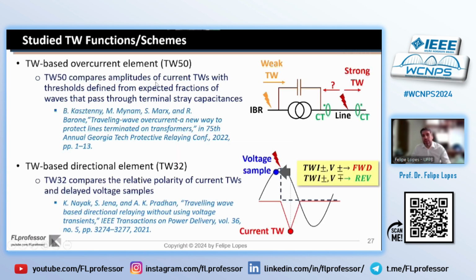The overcurrent traveling wave element compares amplitudes of currents with thresholds, which are defined from expected fractions of waves that pass through terminal stray capacitances. Such an element was presented in this paper. And the idea is if there is a line fault, it is expected to measure a strong wavefront here. But if there is a fault behind the transformer, only weak wavefronts will be measured, because they will pass through the stray capacitance of the transformer, and it will attenuate these wavefronts in such a way that we can distinguish cases of line faults and faults behind the transformer.